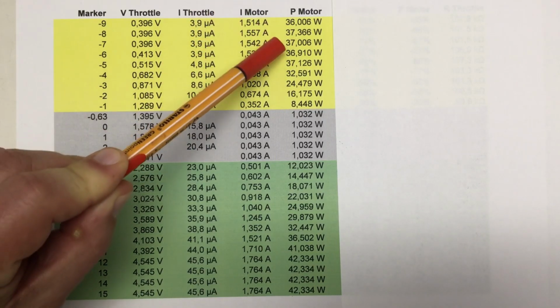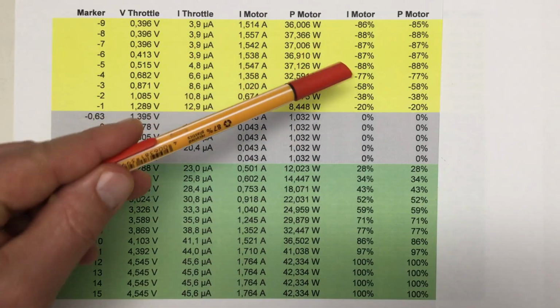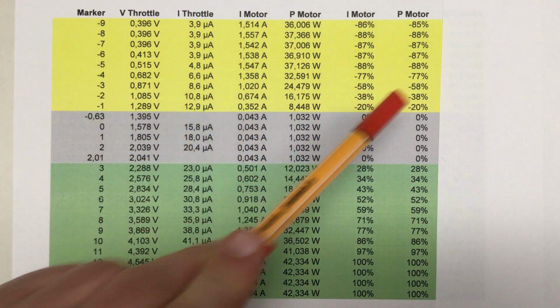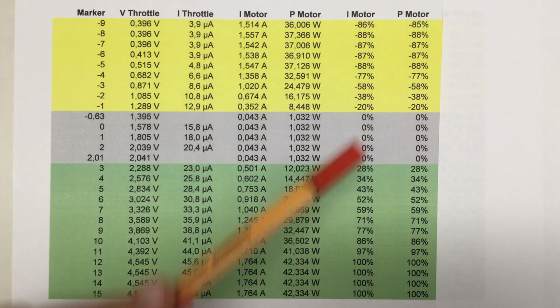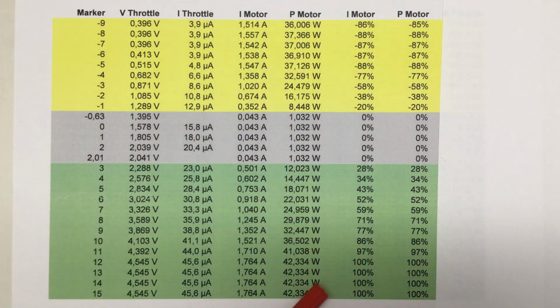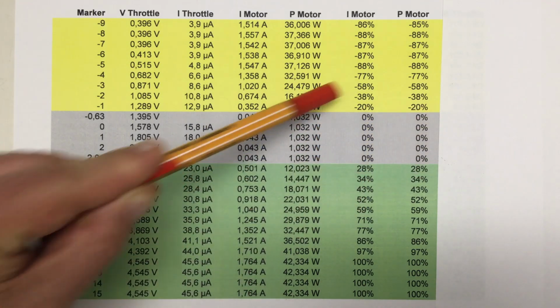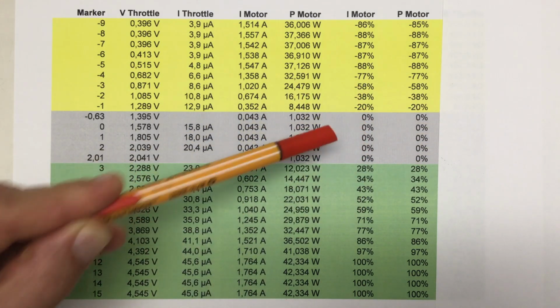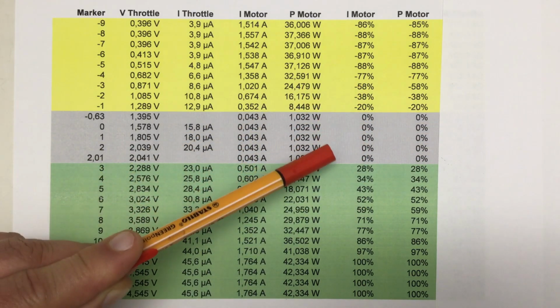I also expressed the motor current and the motor power as percentages of the maximum values we measured at markers 12, 13, 14 and 15. That would be 1.764 amps and 42.334 watts. I manually set the values to 0 where the motor was not turning at all.